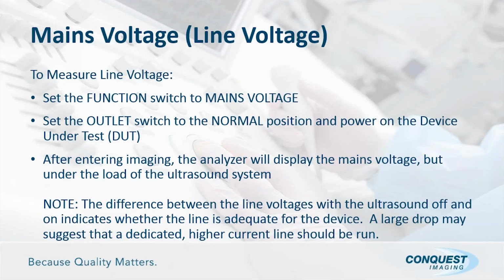And the difference between the line voltages with the ultrasound off and on indicates whether the line is adequate for the device. So if you have a large drop in current or voltage as you turn on the system, that may indicate that the circuit you're on has too much load on it, and you may need to have it rewired or introduce a new circuit such that the ultrasound is isolated on one circuit to limit this voltage drop.